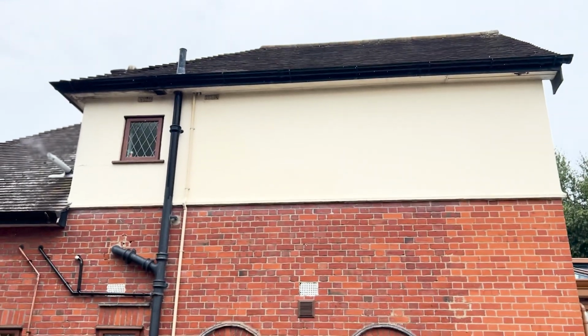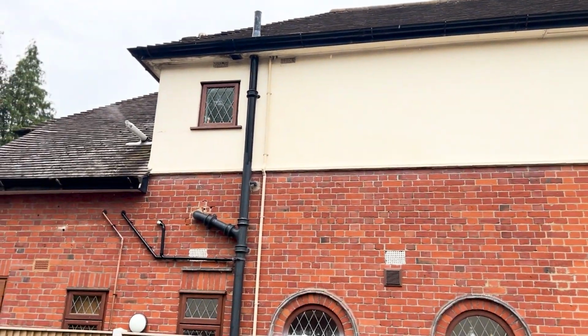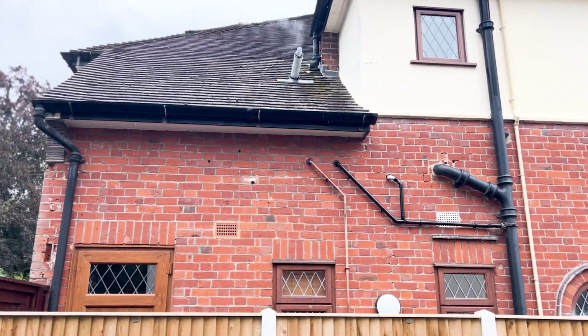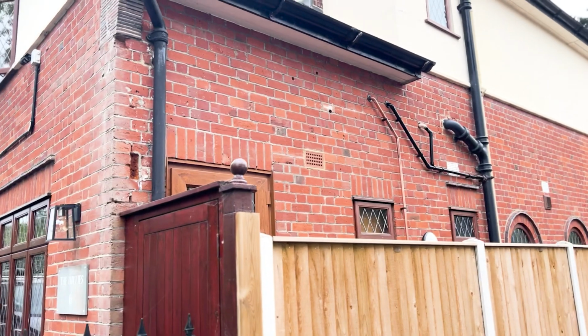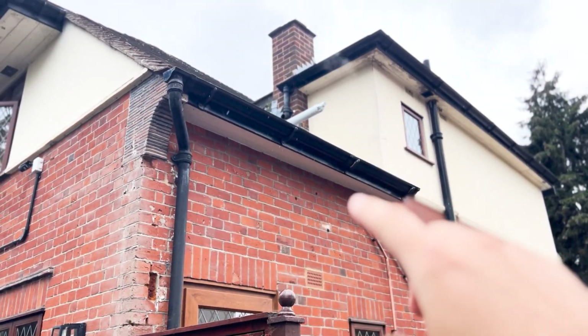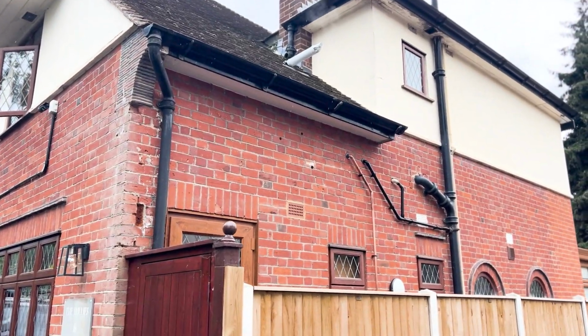So come out there and you can see that's our flue, coming up. It's a bit longer than what we wanted, but when I was speaking to the roofer, we were doing the measurements, and then I think he just moved it out another 100mm or whatever, and it's just one of them. But with Vaillants, you can do that. It can come out horizontal like that, so there's no problem with that, before I get the flue police on at me.